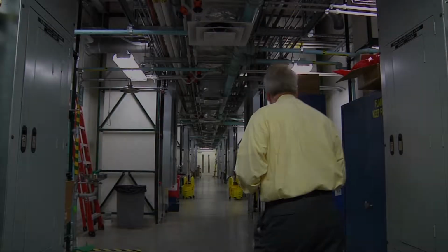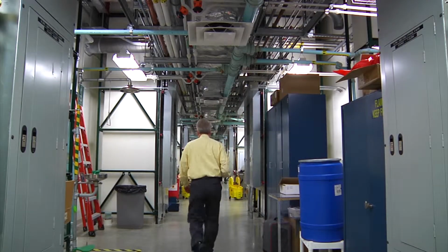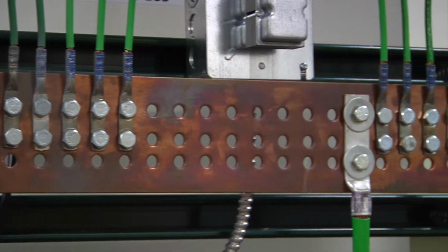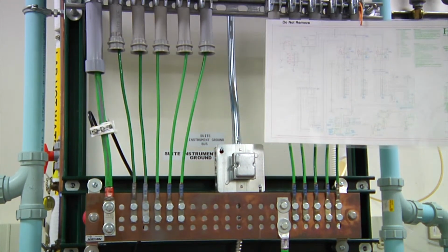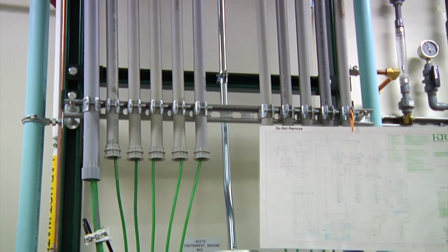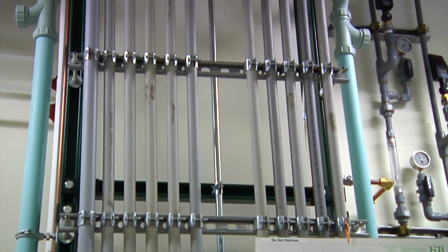The galleys are a very important part of a laboratory space in the facility. They have two main functions. One is they are the spot that all of the utilities for the building run through. So that gives us a very easy place to access those utilities.